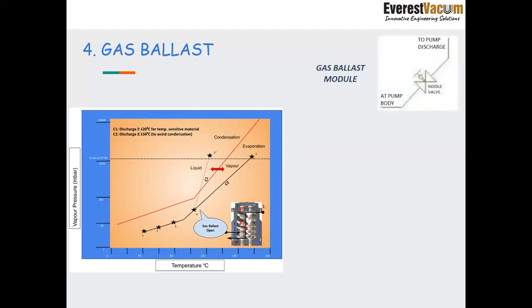So this is what the gas ballast module looks like. From the pump discharge, we have one needle valve which controls the amount of gas to be purged into the pump body.